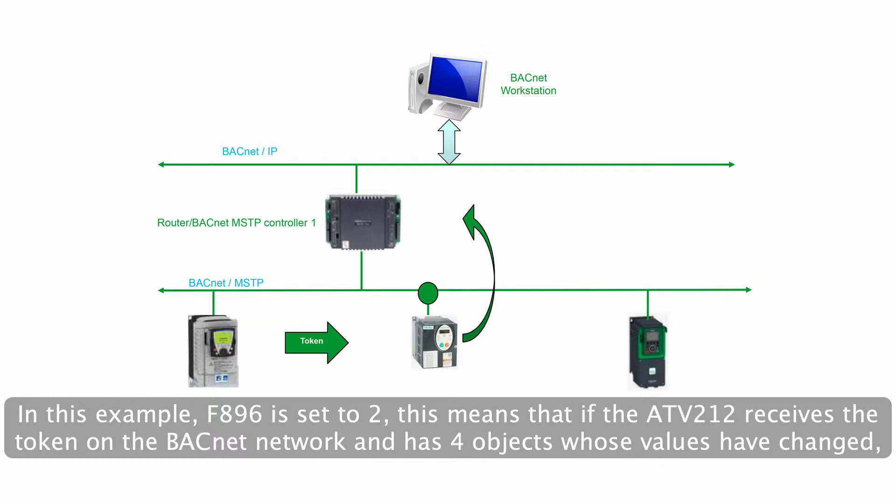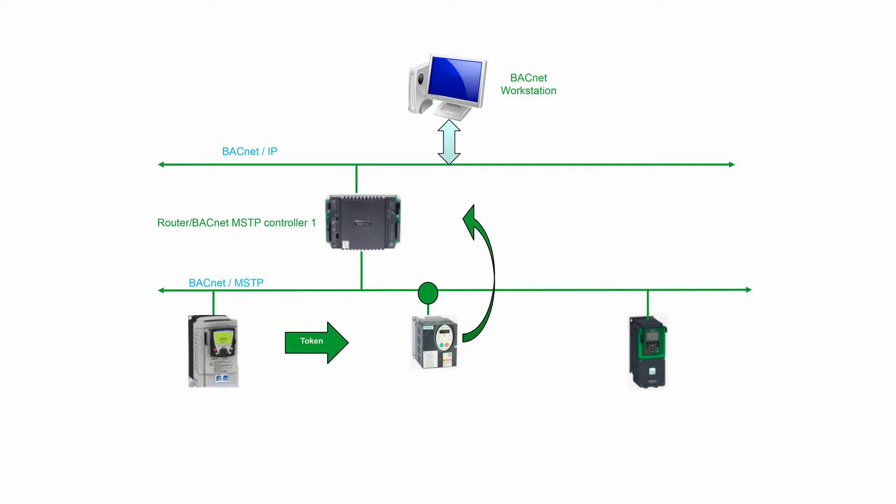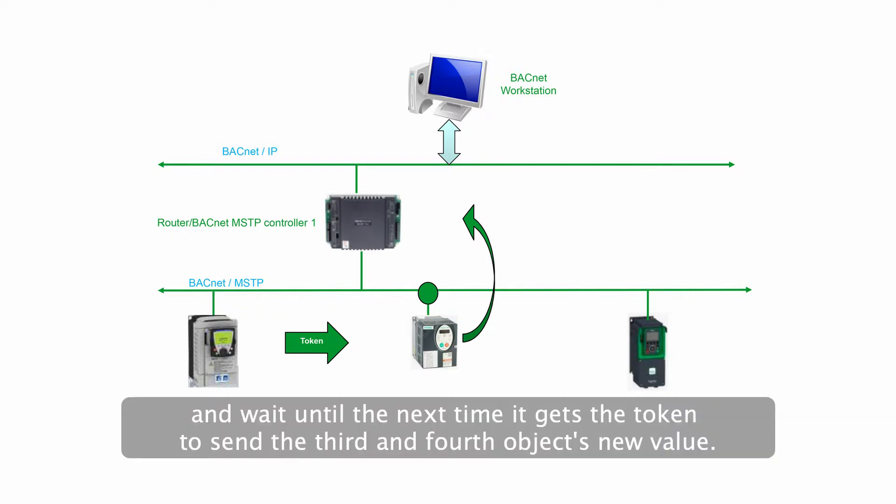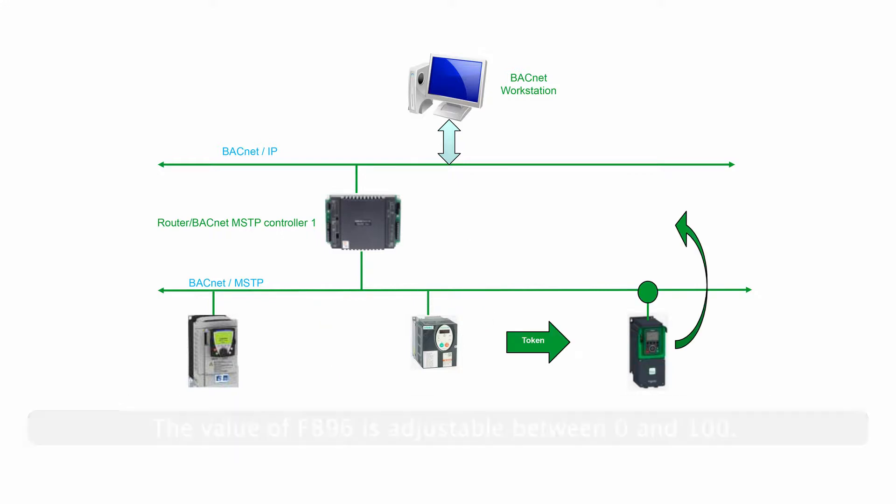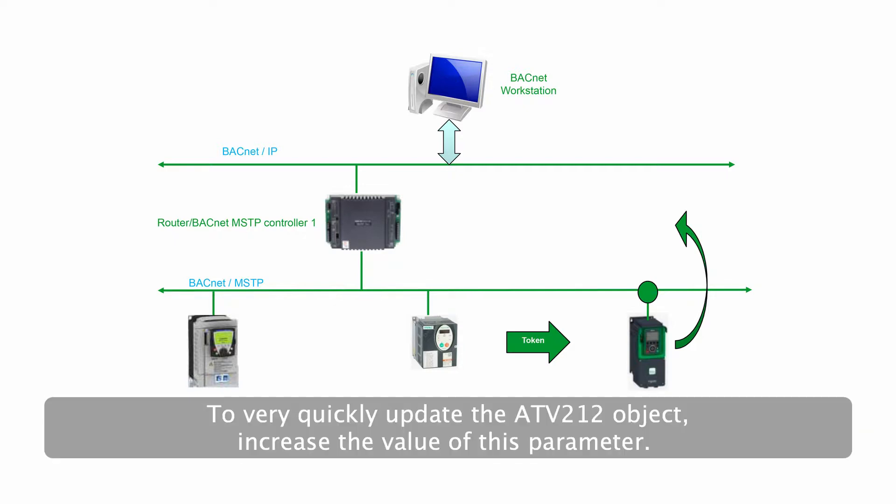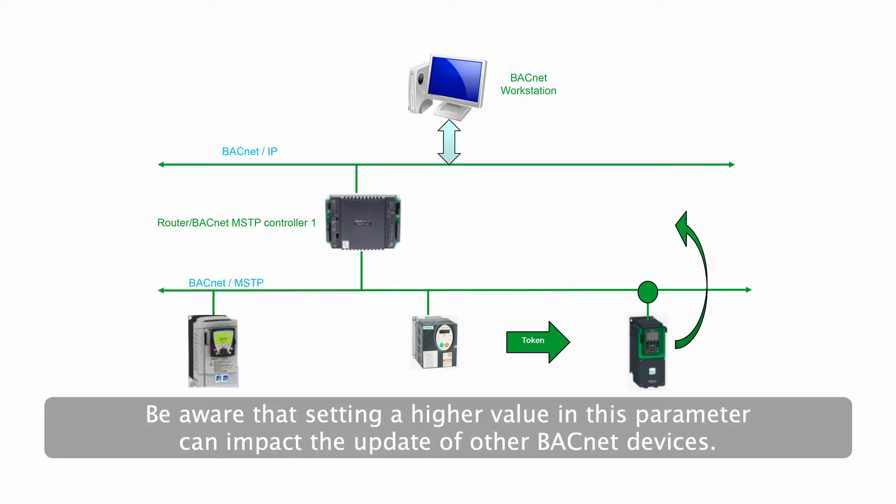This means that if the ATV212 receives the token on the BACnet network and has four objects whose values have changed, it will send the new values of the first and second objects, and wait until the next time it gets the token to send the third and fourth object's new value. The value of F896 is adjustable between 0 and 100. To very quickly update the ATV212 object, increase the value of this parameter. Be aware that setting a higher value in this parameter can impact the update of other BACnet devices.